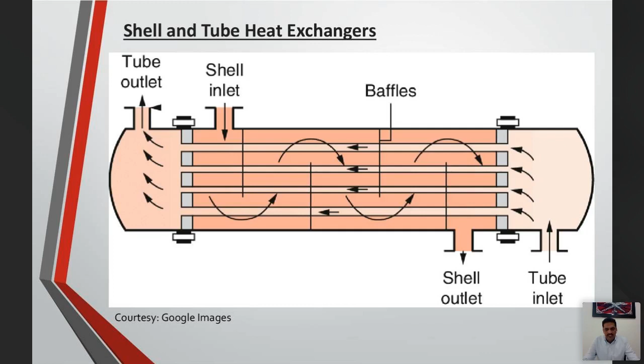When you talk about heat exchanger design, there are two aspects we have to look into: one is thermal design, another one is mechanical design. What is thermal design? Thermal design is to calculate the heat balance, heat transfer area, and sizing of the equipment. First, we have to see how much heat is required to warm or cool the fluid. Based on that, you have to see what the temperature difference is. From the temperature difference, you will get how much heat transfer area you require. Once you find out the heat transfer area, you will size up the equipment, for example, 2 meter long, 3 meter diameter, something like that.